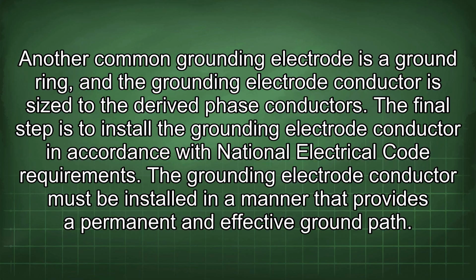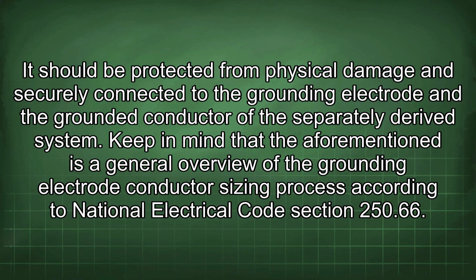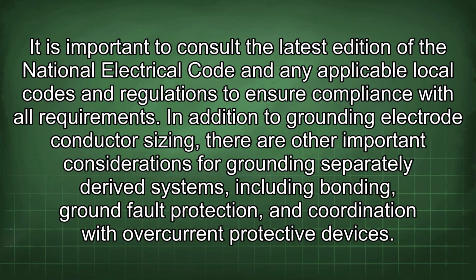The final step is to install the grounding electrode conductor in accordance with National Electrical Code requirements. The grounding electrode conductor must be installed in a manner that provides a permanent and effective ground path. It should be protected from physical damage and securely connected to the grounding electrode and the grounded conductor of the separately derived system. Keep in mind that the aforementioned is a general overview of the grounding electrode conductor sizing process according to National Electrical Code Section 250.66. It is important to consult the latest edition of the National Electrical Code and any applicable local codes and regulations to ensure compliance with all requirements.